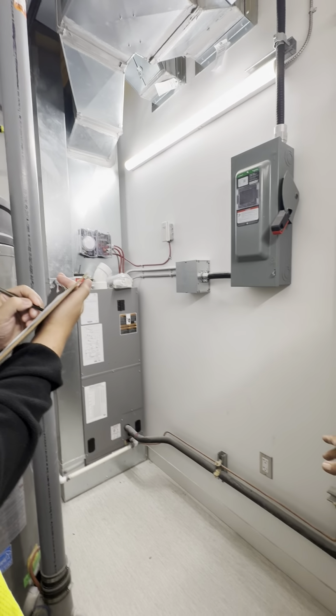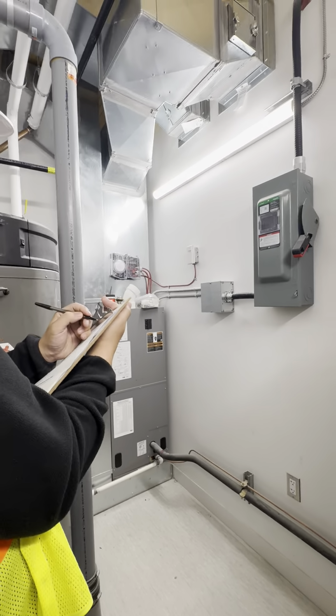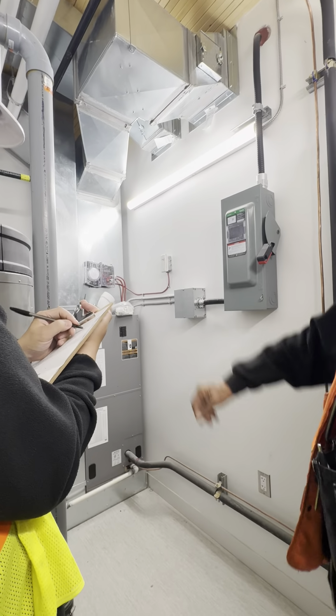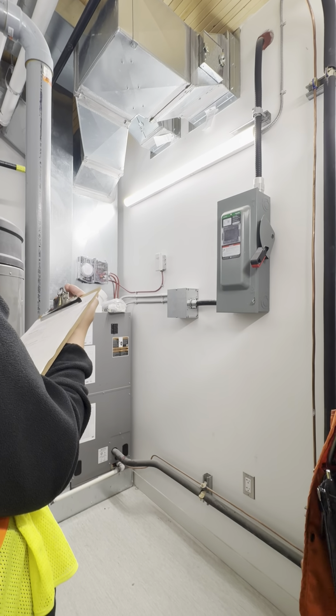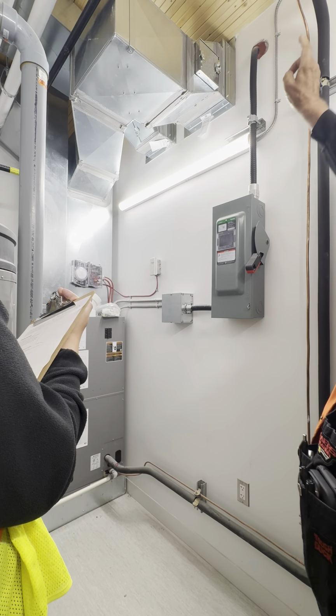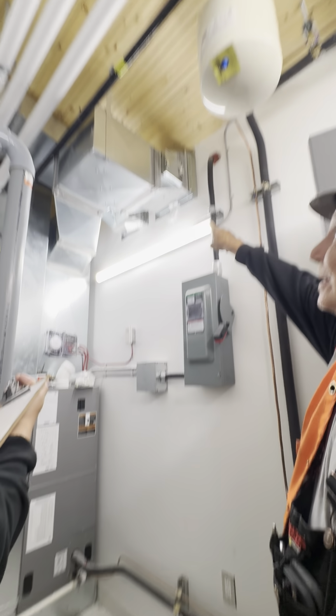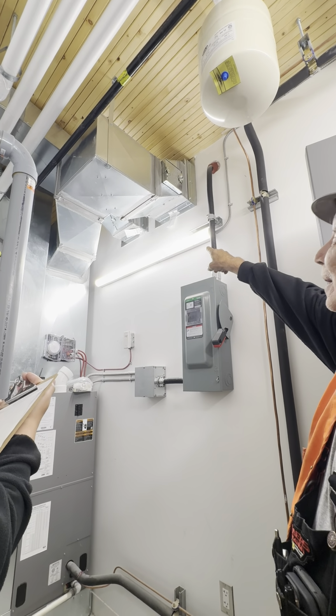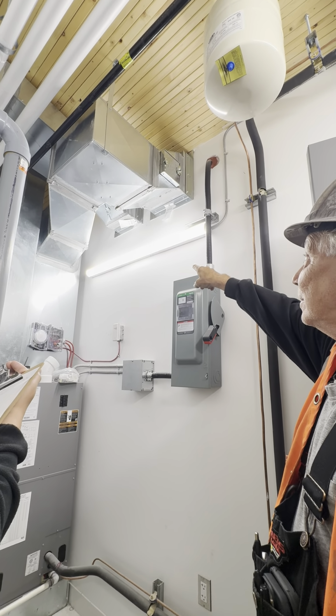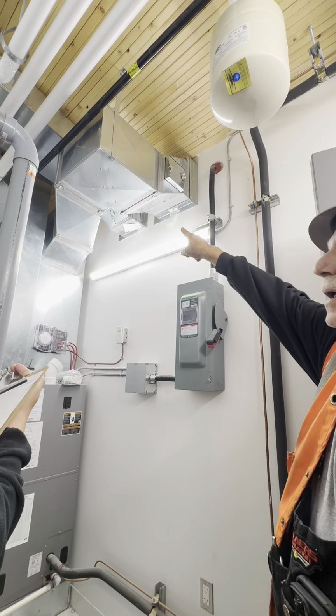It's different, because the mechanical room doesn't go to the common area, it goes into the suite. So it doesn't go into a common hallway, so now you can have regular fire dampers. Behind that door, you have a fire damper, see there's a tag on it saying it was tested, by DFC, same with the other one.